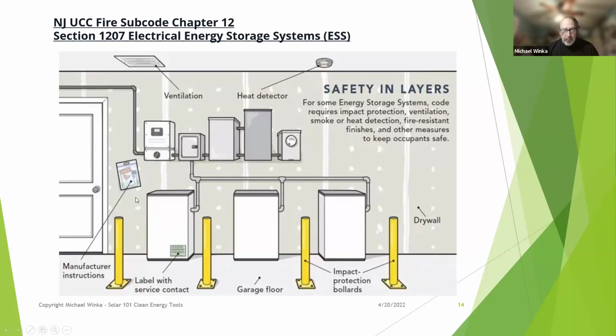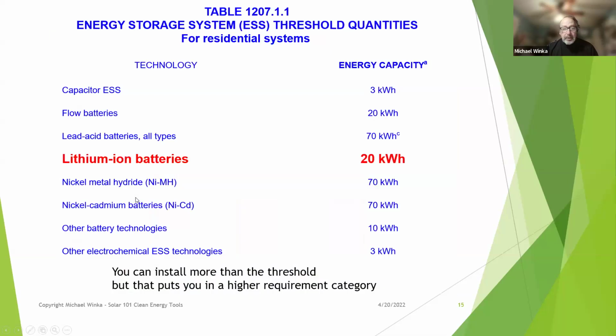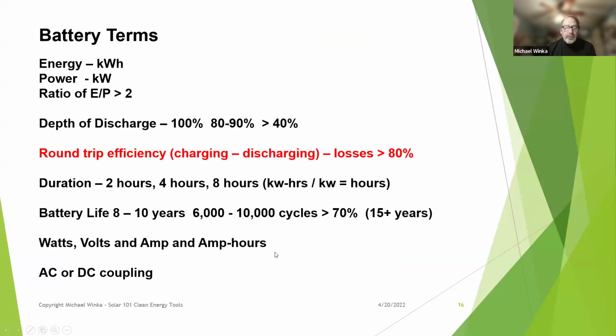If you're thinking about battery storage, talk to the contractor about the current code. There are threshold limits on the amount of batteries that you can install at a residential level. For lithium ion batteries, it's 20 kilowatt hours, which is about the average use of an average home. So you're at the average use here. You can install more, but that puts you into a higher category in terms of safety and the other things that you have to do with the system. So a couple more terms in addition to energy, kilowatt hours, and power, kW. You want to look for a battery system that has an energy to power ratio that's greater than 2. You'll see that as a selling point.